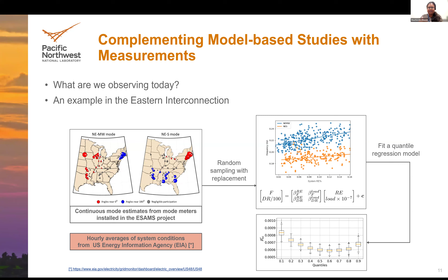So we got about a year of continuous mode estimates from the project, then took hourly averages of system conditions from the US EIA website, and tried to investigate whether correlation exists between the observed frequency and damping ratio estimates of the mode and changing system conditions. We selected 2 particular system conditions: the load, so how frequency and damping ratio vary with system load, and how they vary with renewable energy penetration. Again, there are limitations because the reported renewable energy penetration is only what is being metered, the utility-connected ones, and we don't have visibility of behind-the-meter resources. Typically, all of the reported scenarios had renewable energy penetration less than 10%.